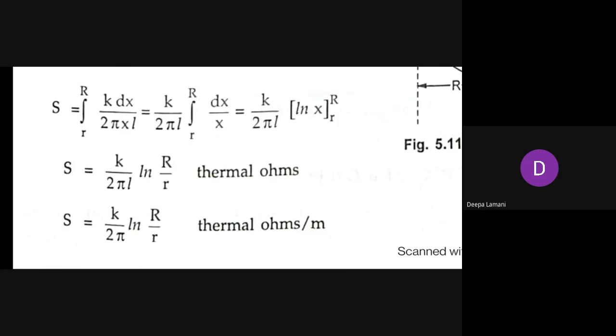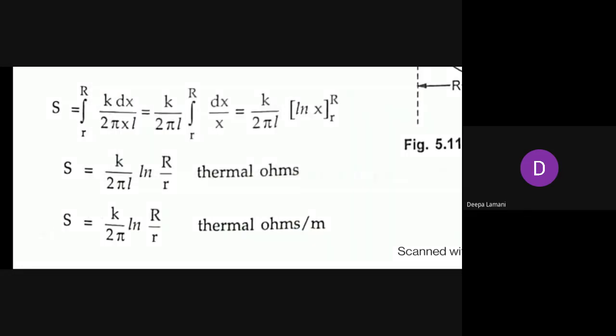The formula for thermal resistance of a single core cable is: S = (k / 2π) · ln(R/r), where capital R is the outermost radius and small r is the innermost radius. This is our final formula for thermal resistance of a single core cable.